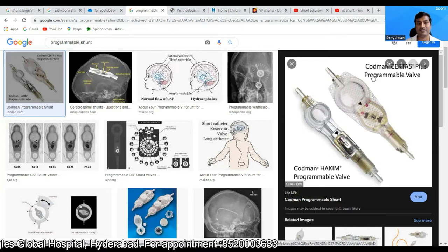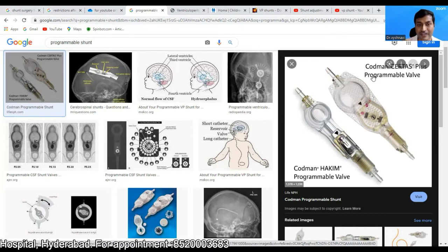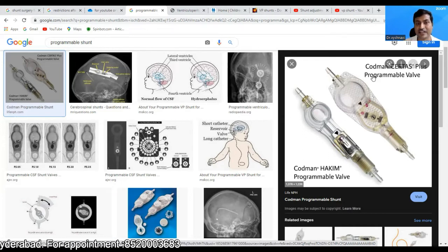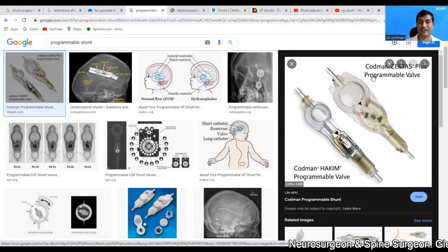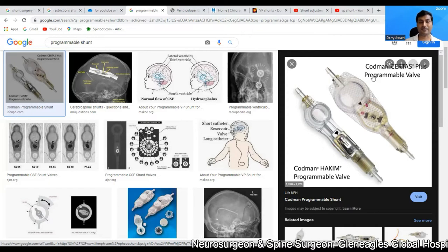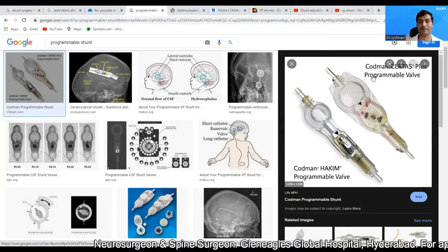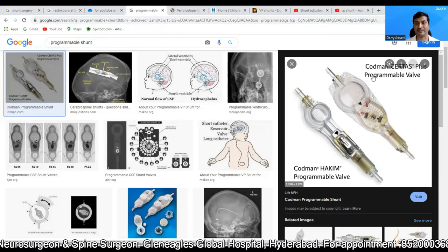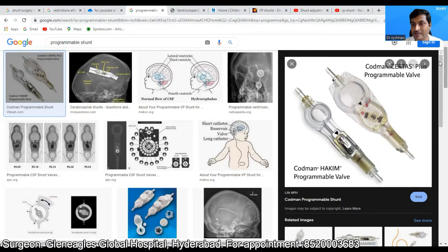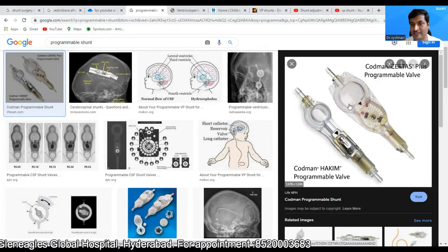If you put a fixed pressure shunt in these patients and the shunt over drains or under drains, you will have to revise the shunt — you will have to redo the shunt, placing it with a higher or lower pressure. To circumvent this, we have a programmable shunt.